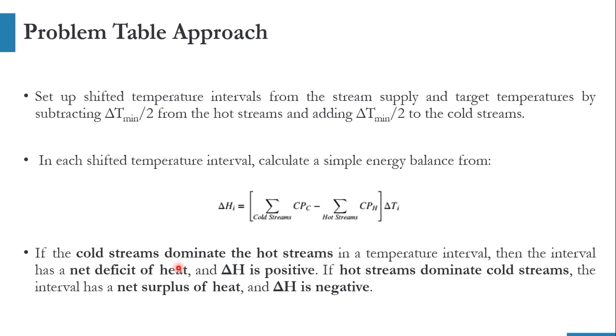The problem table approach is comparatively easier than the graphical method. We will be using the shifted temperature intervals from the stream supply. For the hot stream, we will subtract delta T min over 2 from the values, and for the cold stream, we will add delta T min over 2. In each shifted temperature interval, we calculate a simple energy balance: delta H_i equals (CP of C minus CP of H) multiplied by delta T_i.